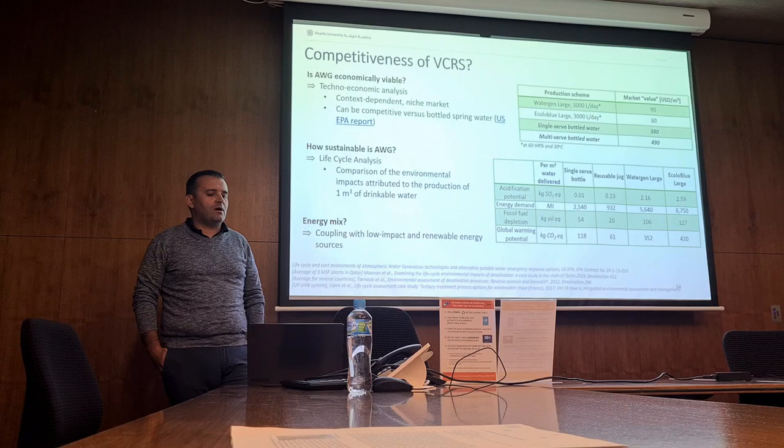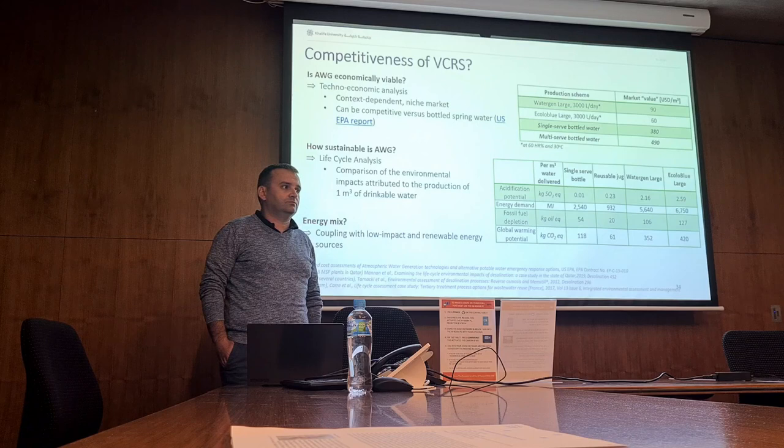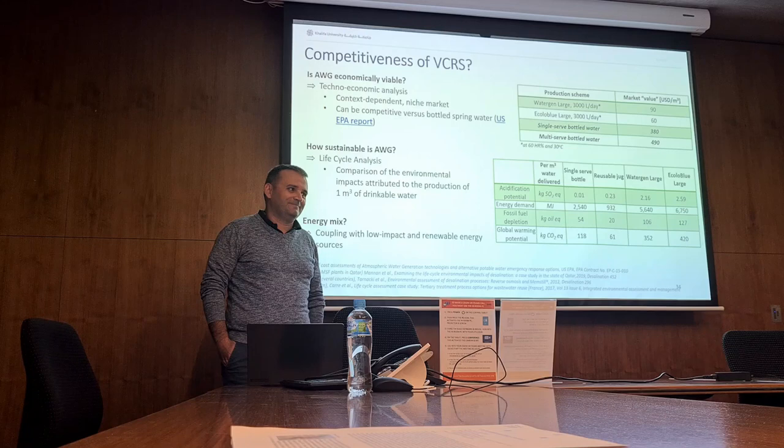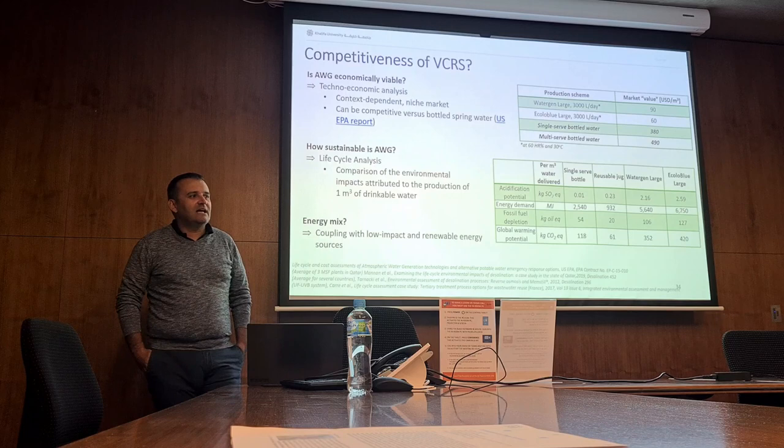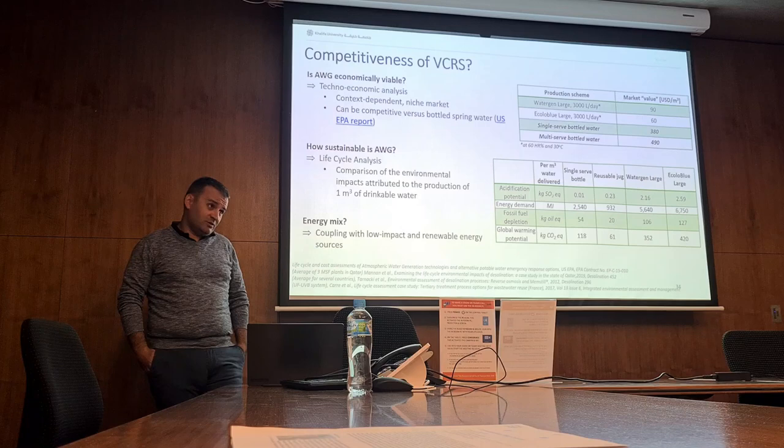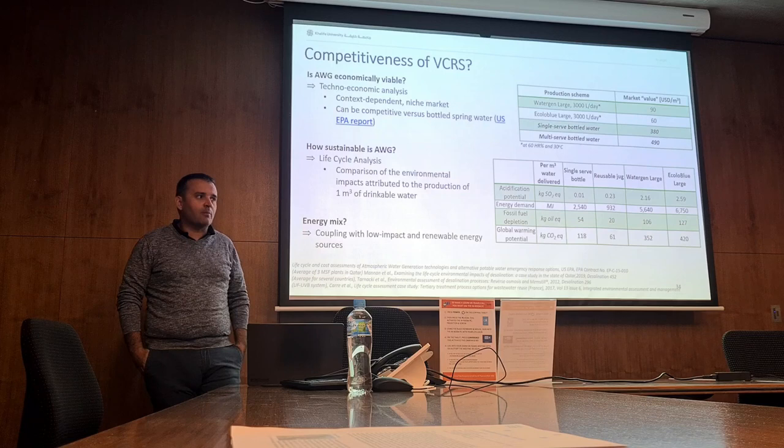Do you pay a lot of money for maintenance of the equipment, knowing the sand storms and all that, the overheating? Roughly, what's the percentage of that? I'm not sure exactly, but it's significant. Because of the heat, because of the sands, because of the very large variation of temperature day and night, we have lots of failures, which we knew from the start, but which represent a major maintenance cost to the operation.